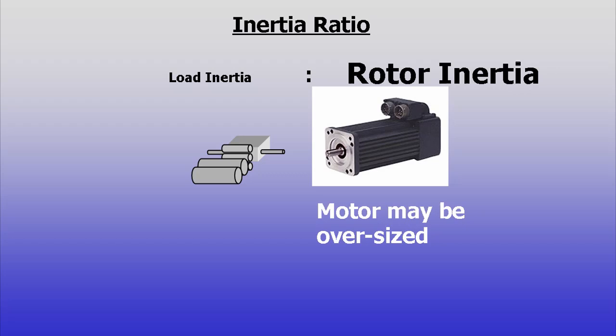On the other hand, if the rotor inertia nears that of the load, it may mean that the motor is larger than it needs to be.